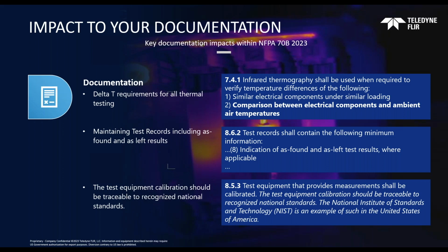There's a whole laundry list of different things the test record should contain, but I wanted to point out number 8 on that list: the indication of as-found and as-left test results where applicable. Where this pertains to thermography, if we identify a failure, we're identifying that as found, and if any corrective action was performed, we need to document that we made the repair, as left, when we left that equipment at the completed state or completed repair. Being able to tie all those things together, understand that the electrical maintenance program has specific requirements on documenting those things. I just wanted to call out specifically this as-found and as-left.